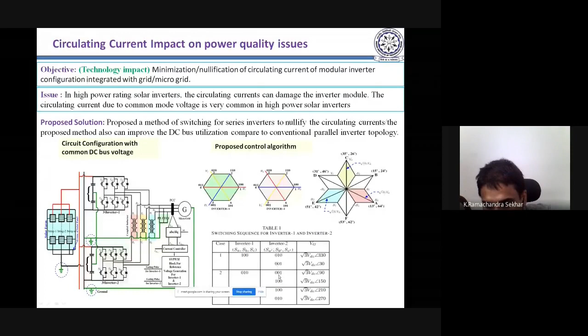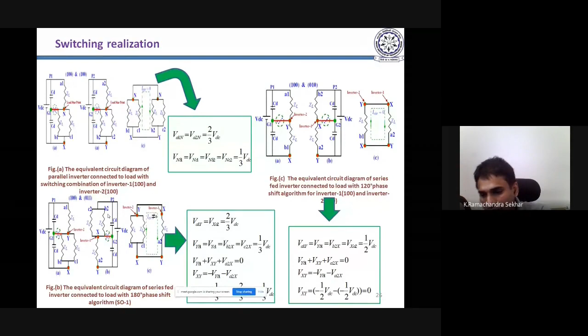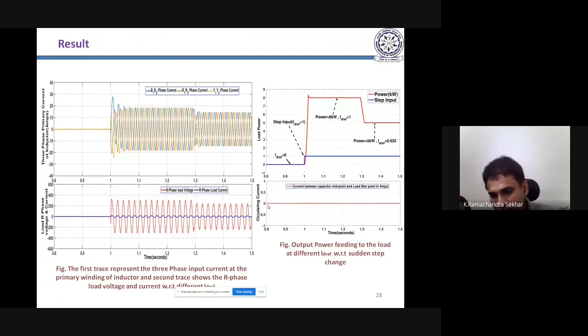We found certain switching states that give zero common mode voltage. So we identified the switching states of inverter 1 and inverter 2 where the common mode voltage goes to zero, modeling the impedance of the AC and DC sides to achieve this. This way we demonstrated that we can ground the DC bus while keeping circulating current at zero -- meaning the capacitor midpoint voltage and the AC side star point voltage stay at zero all the time.